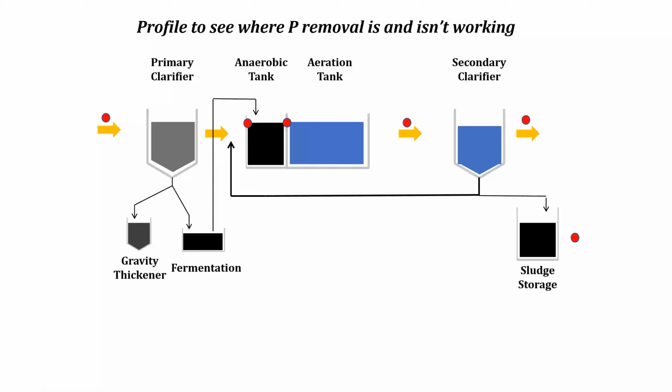Now you can do it constantly, of course. You're going to measure this concentration, and then you have the plant flow versus the gallons per minute coming out of the fermenter. So that'll give you your pounds to pounds. There is a recommended return rate in pounds, and you want at least twice as many pounds of VFAs. Now, of course, if you have nitrates and the denitrifiers are consuming your volatile fatty acids, you need enough to satisfy them plus 2 times. Hopefully that answers the question.